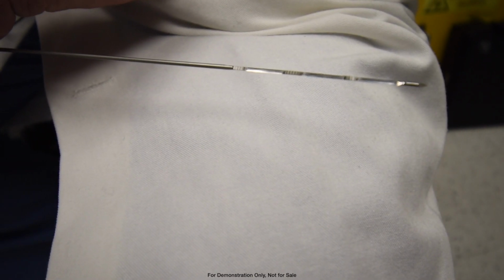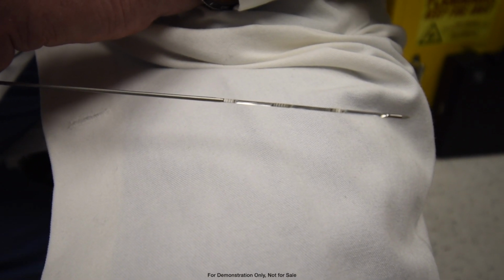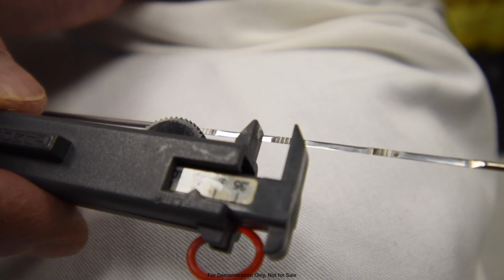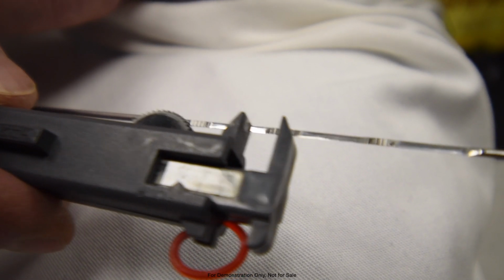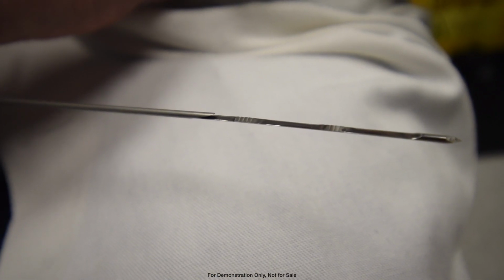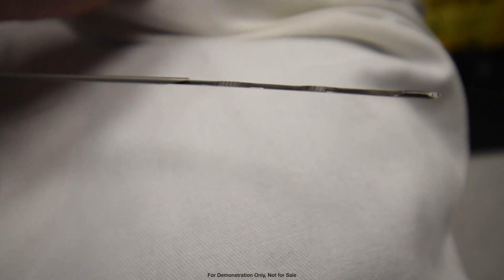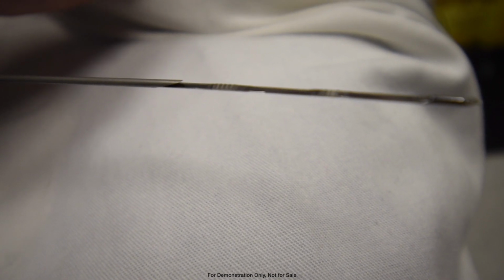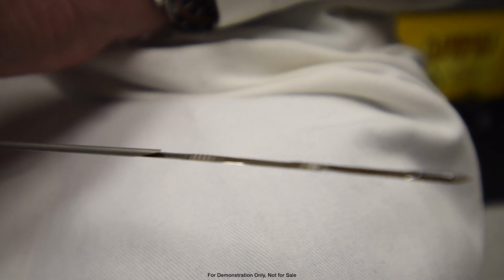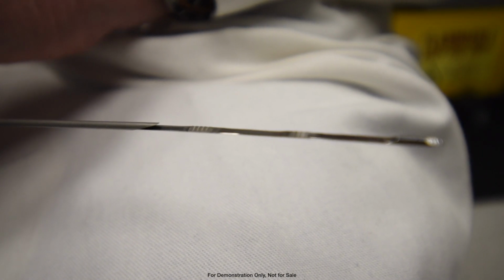By creating a needle with a 6-centimeter core bed, that will allow us to biopsy up to 95% of all prostates. As you can see, there are ridges along the core bed. What these ridges do is they hold the tissue in place, thus ensuring the entire length that one wishes to obtain. For example, if the length of the prostate is 5 centimeters and one wants a 5-centimeter specimen, then this will get the entire 5 centimeters. Testing in the lab with animal tissue has demonstrated that we do indeed get over 90% of the tissue that we require.